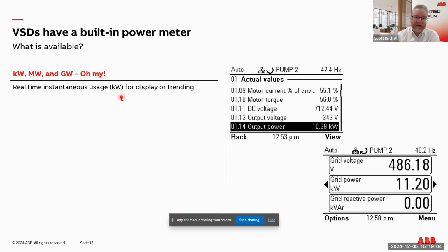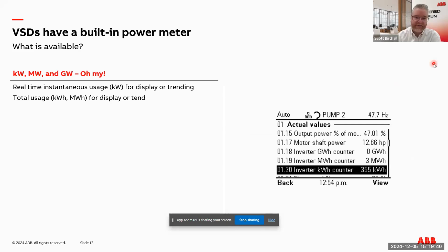So first thing you can do is you can read instantaneous kilowatt. So I can see the typical drive, that's not going to be input kilowatts. That's actually going to be output kilowatts to the motor. But if you added 3% of it to it for the losses of the drive, that'll give you roughly what the input kilowatts are. Some drives are known as active front end drives, ultra low harmonic drives. They can actually give you grid input power also. But you can get that input power. You can display it on the drive. You can integrate to it via Modbus or BACnet, and then you can trend that in the building automation system.